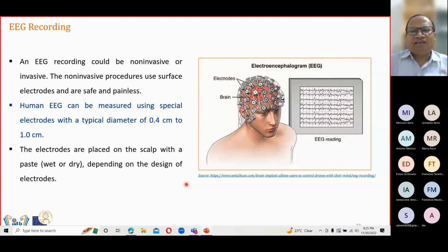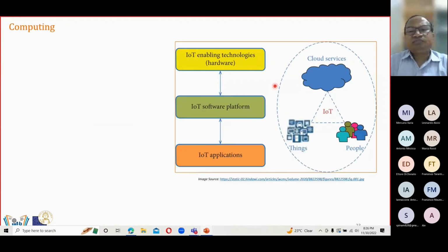All right, so see, the purpose of the electrode is to receive electrical signal, and the scalp is a body, the scalp has a skin area. We want flow of electrons, the electrical signal. So we want a conductive path. To provide a conductive path, we put some gel, some material which is a liquid or some paste, some gel kind of material that provides a conductive path so that the signals coming from the brain can be captured by those electrodes. This is why we put that.